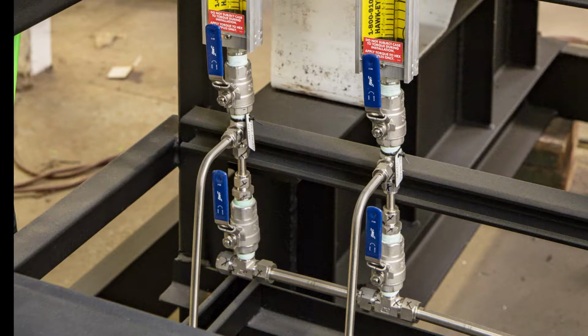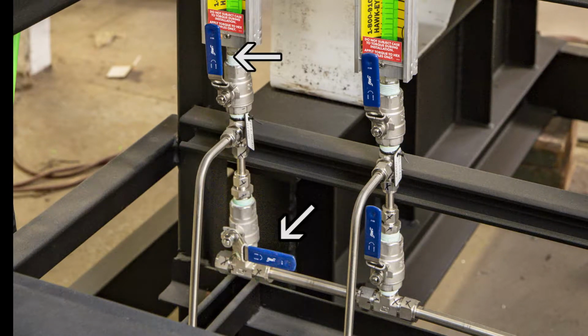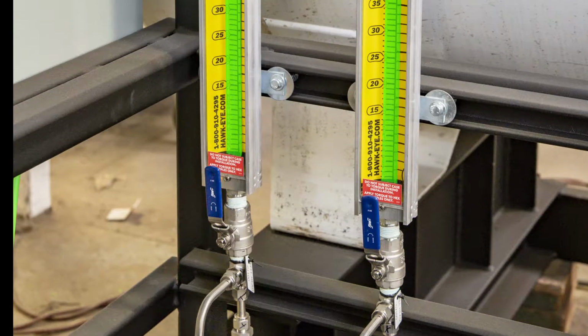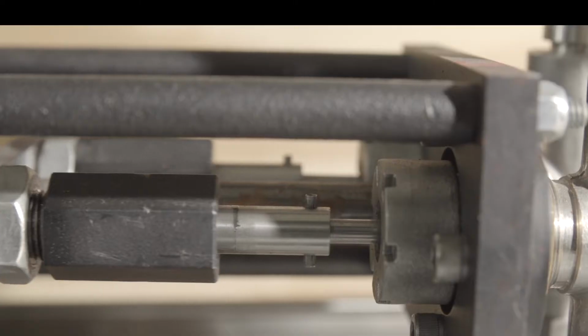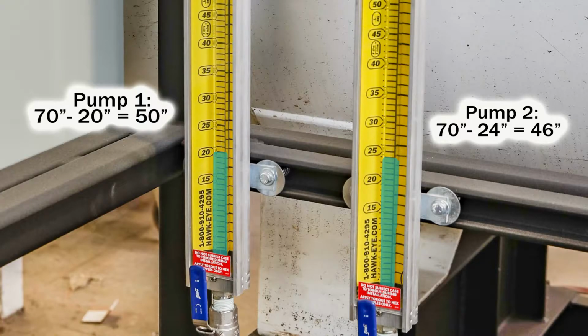For the first pump to be tested, close the pump supply valve and open the sight glass valve. This will have the pump drawing from the sight glass only. Record the difference in liquid level in the sight glass over 1 minute. Repeat this for each chemical pump.